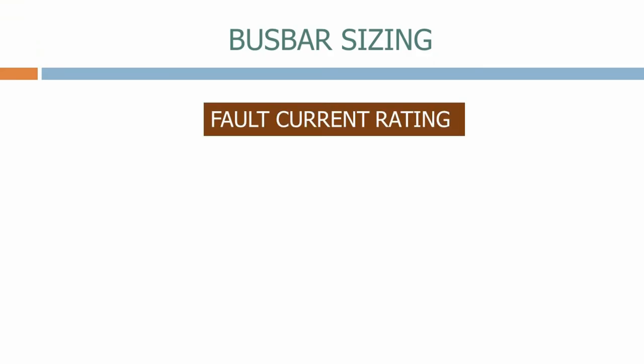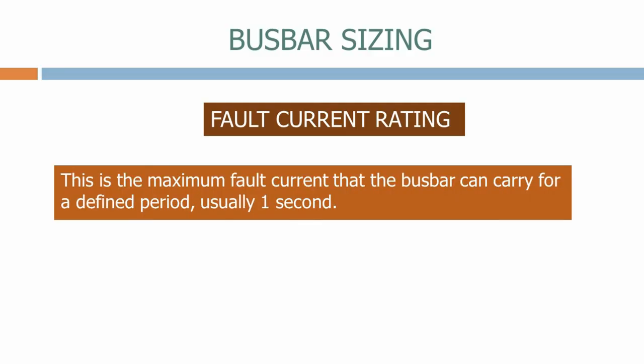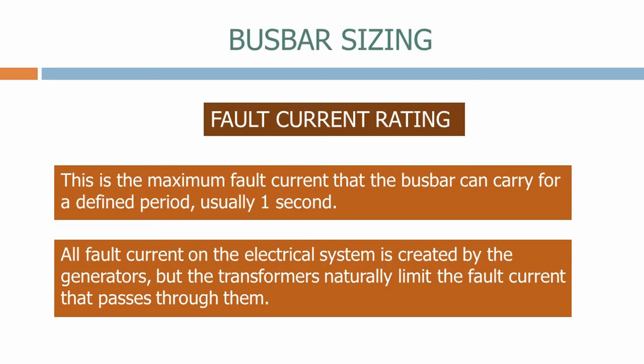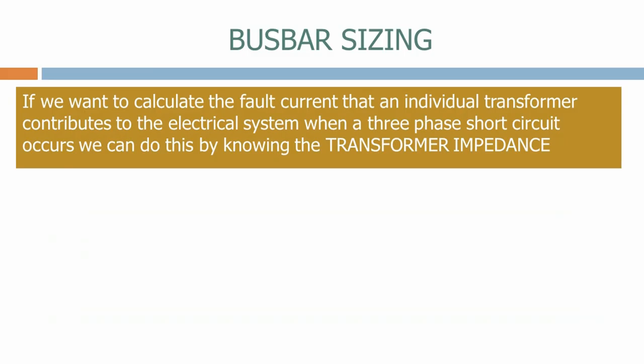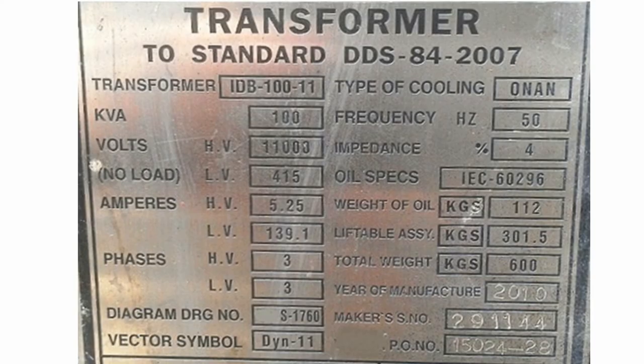The other main element we use to define busbars is the fault current rating. This is the maximum fault current that the busbar can carry for a defined period, usually one second. All fault current on the electrical system is created by the generators, but the transformers naturally limit the fault current that passes through them. Here's a rating plate for a 100 kVA, 11000 to 415 volt transformer. For this transformer the impedance is 4%.